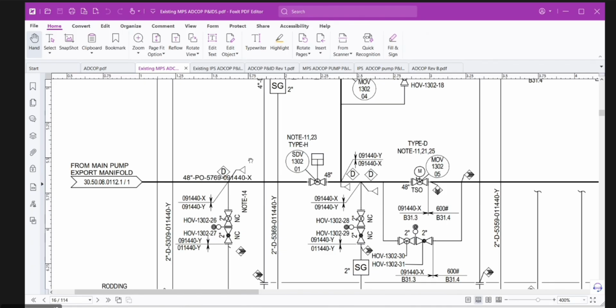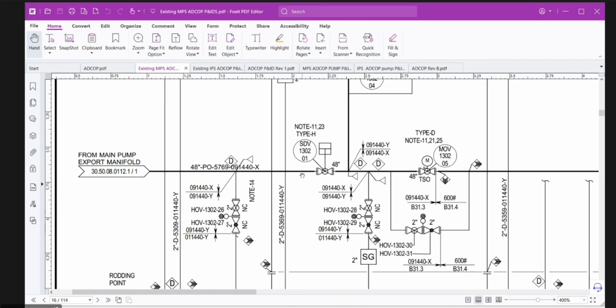But for that we have added in the suction line. Where is the pipe rupture, the spec breakage after this MOV, right? 900 and 600. Yes, I think up to 900 it will withstand the pump maximum shut-off pressure. No, after calculation, the pressure will exceed the 900. Okay, because the shut-off pressure of the existing pump is more than 900.